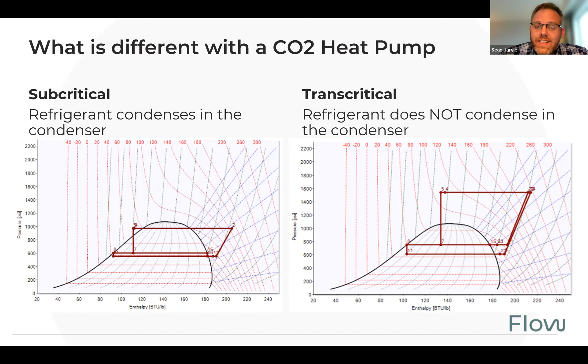Now, every standard HFC, HFO system is a condensing system where we always have to get beyond and inside that vapor dome. A transcritical system says, now we don't really care about that anymore. And we push the pressure up as high as we can. And now we have that entire top line to draw heat off of. Our capacity is directly proportional to the difference in enthalpy. So the more difference in enthalpy you can extract, the more capacity you can extract. And so with a transcritical system, we can extract anywhere from 40% to 70% more heat per unit of power than we could with a subcritical type system, which is really, really amazing. And that's the fundamentals behind why CO2 heat pumps can do so well.